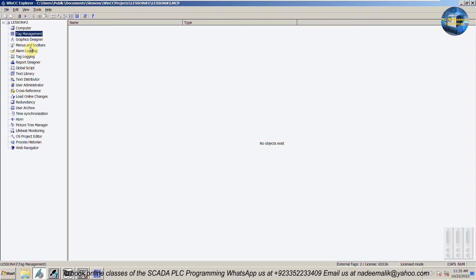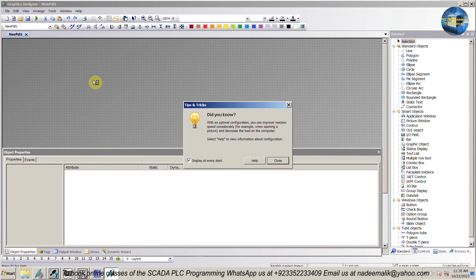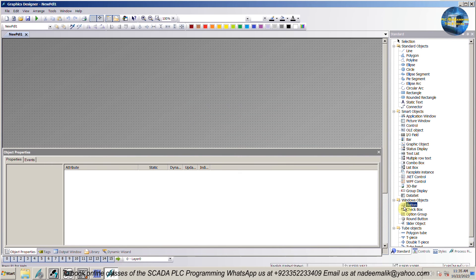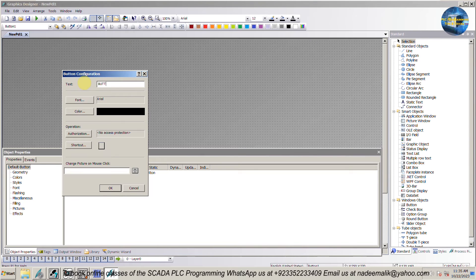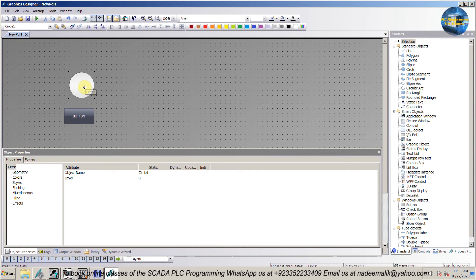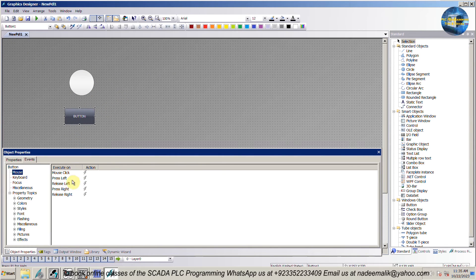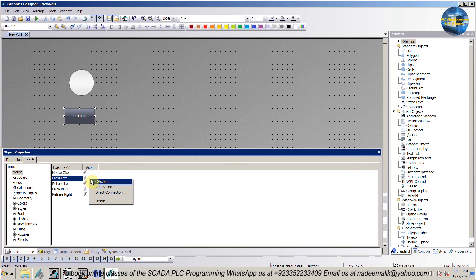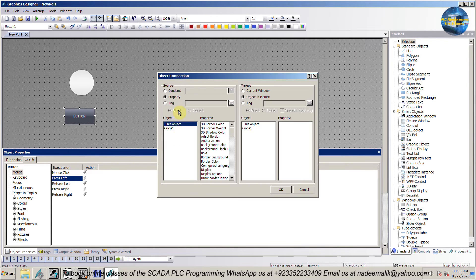We have created the tags. Next we will open the graphic designer. First we will insert a button on the screen and give it any suitable name. We will assign the input M10.0 to this button later. Next we will draw a circle on the screen — this will indicate the output bit status. Select the button and click the press left option, which refers to the left mouse button click on this button. Right-click and select the direct connection option.